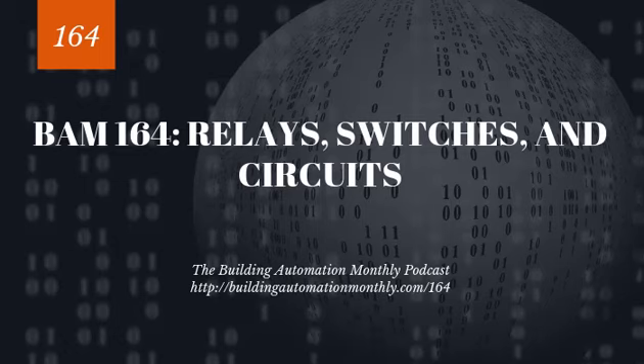Your controllers tend to cost anywhere from $200 to $1,000, whereas a RIB U1C or an IDEC single pole double throw is going to cost you around $10, so $5 to $10. So you blow a relay, not such a big deal. You blow a $200 controller, it is a big deal. Also, it provides isolation that makes it easier for you to troubleshoot, especially if you're using RIB U1Cs that have an indicator on them, or even some IDEC that have indicators on them. It shows you whether that relay is triggered or not.